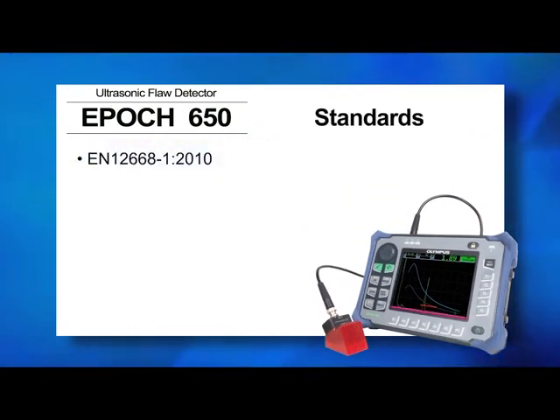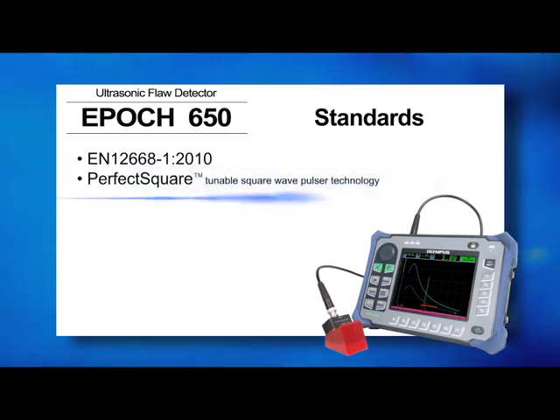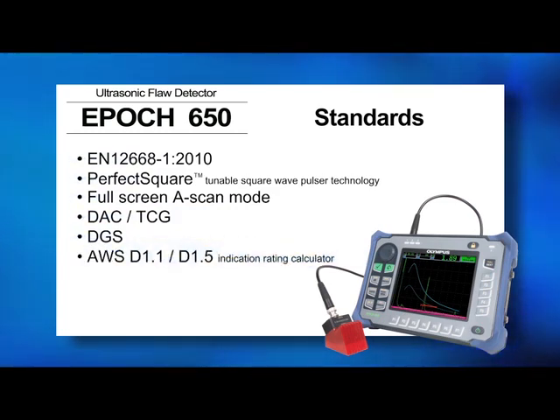It comes standard with our PerfectSquare tunable square wave pulser technology, a full-screen A-scan mode, and multiple inspection technique features, such as DAC-TCG, DGS, and our AWS D1.1 / D1.5 Indication Rating Calculator.